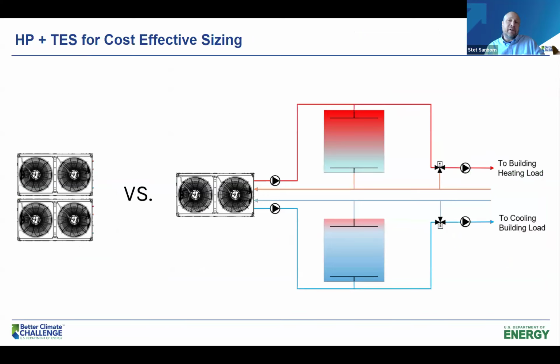And this is the sort of comparison that we did for our project. So we could either size a heat pump for the absolute peak hour, peak load, everyone's happy, it's very comfortable, but more expensive. Or in the case of the system that we designed, we did a smaller heat pump with thermal storage on the hot water side, thermal storage on the chilled water side. And that solution actually came out cheaper on day one and to operate than the two heat pumps. And if you think about it from a life cycle investment, those tanks of water or phase change material or whatever material you select for thermal storage, those can sit there for a very long time without needing to get replaced, compared to a heat pump that typically has a 15-ish year lifespan in the commercial sector.